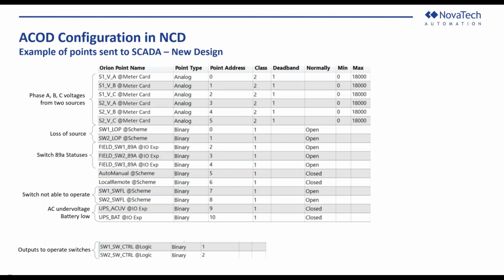And ACOD can run independently as it's a complete package, but also it can report to SCADA. And this is a set of points that you could expect to see on the DNP server port going up to a SCADA system or whatever you may have. So there could be the voltages for each of the phases for each source 1 and source 2. Below that, we have the loss of potential points that we were talking about. If ACOD recognizes there's a loss of potential, then those alarms would be tripped.